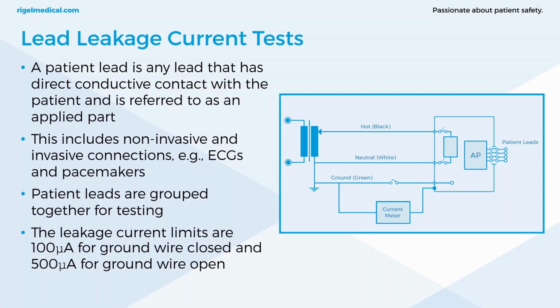Now, in NFPA 99, the patient leads are grouped together for testing. This wasn't always the case, so looking through some of the previous versions of NFPA 99, it does state that individual applied parts to ground must be measured. However, in the last few editions of NFPA 99, including this one, 2021, patient leads are always grouped together for testing. So saving yourself some time there. That's what NFPA 99 recommends. The leakage limits are total leakage limits. So 100 microamps for ground wire closed and 500 microamps for ground wire open. So it's performing 2 tests with 2 different fault conditions.